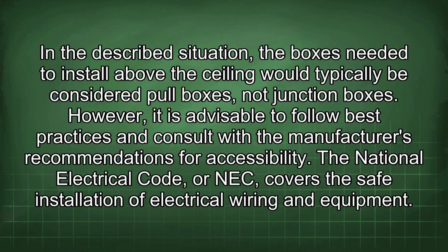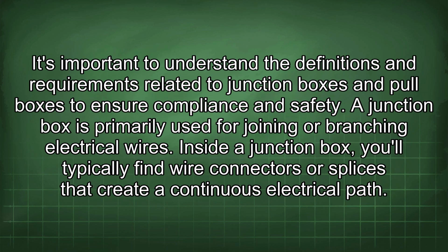In the described situation, the boxes needed to install above the ceiling would typically be considered pull boxes, not junction boxes. However, it is advisable to follow best practices and consult with the manufacturer's recommendations for accessibility. The National Electrical Code, or NEC, covers the safe installation of electrical wiring and equipment. It's important to understand the definitions and requirements related to junction boxes and pull boxes to ensure compliance and safety.